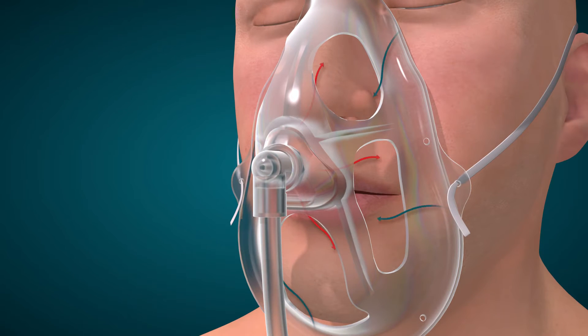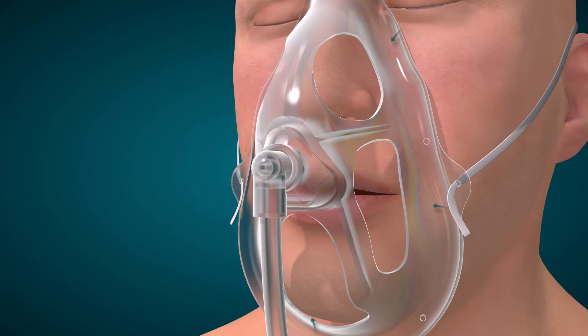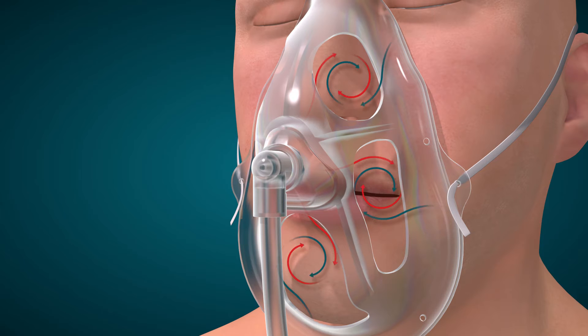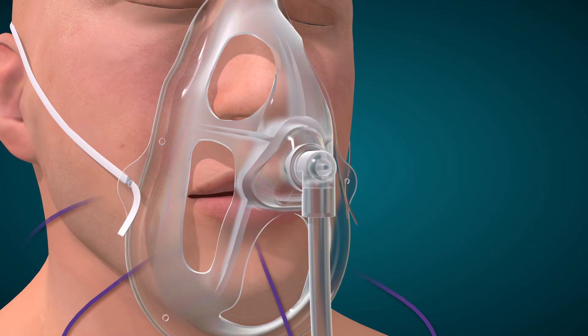During the patient's inhalation, oxygen flow is mixed with room air drawn in through mask openings. Respiratory mechanics and breathing patterns determine how room air combines with the delivered oxygen. The concentration of oxygen received during the breath is a function of the oxygen flow compared to the patient's inspiratory flow and tidal volume. During exhalation, the mask openings allow expired carbon dioxide to escape.